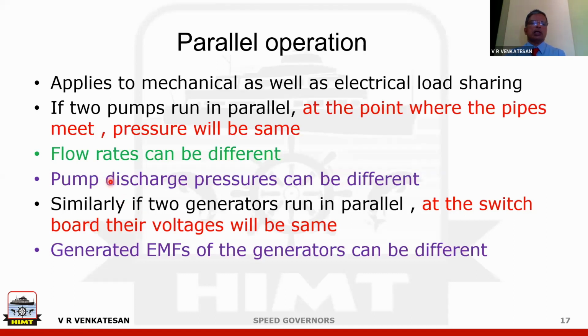So pump discharge pressure can be different. Same way generator EMF can be different. But just like you say, where the pipeline joins, pressure should be same, here voltages must be same. Again, just like you say, pumps can have different flow rates, parallel operation can have different current.